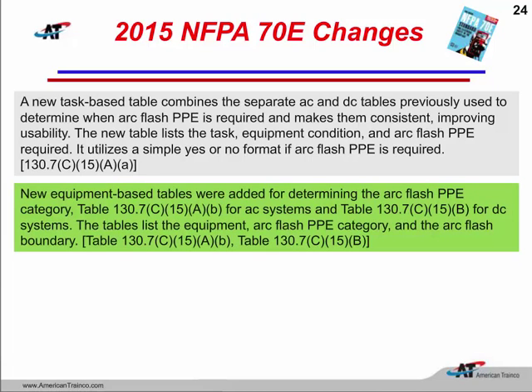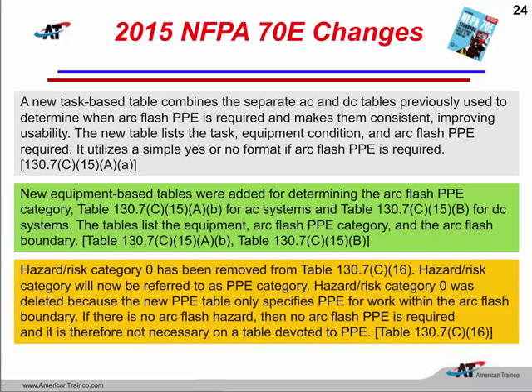Also, they put in for us some new shock tables, and those were revised, and we will see that the prohibited approach boundary is not going to be on those shock tables anymore. All right, so that was also taken into consideration. And hazard risk category 0 has been removed from those tables. So in 2012, we had 5 Arc Flash PPE categories, going from 0 to 4. In 2015, we now have only 4 Arc Flash PPE categories. Hazard risk category 0 was removed. They felt that when the incident energy was below 1.2 calories, the chances of an arc flash occurring were so minimal that no arc flash PPE was required there.